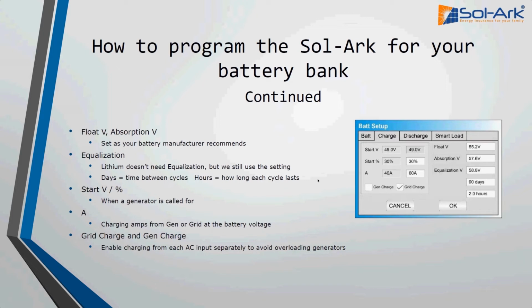All right, moving on to this little checkbox here on the left. Start voltage or start percentage. You're only going to be able to use one, either percent or voltage, at a time, depending on which mode you put the inverter in. And basically this is referring to when we're going to call for a generator. We have a 2-wire start built in to the Sol-Ark. So in this example, if you hit 30% state of charge, then we're going to close that relay and call for a generator to come in and help charge.